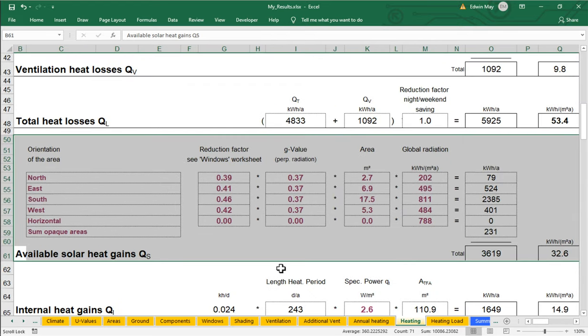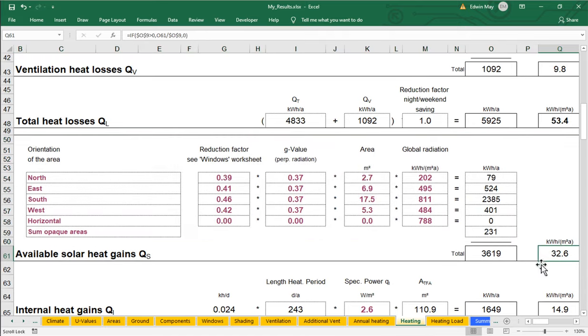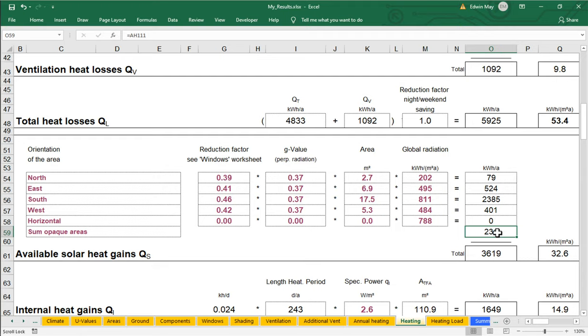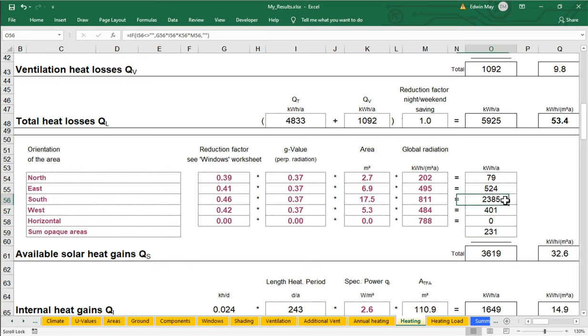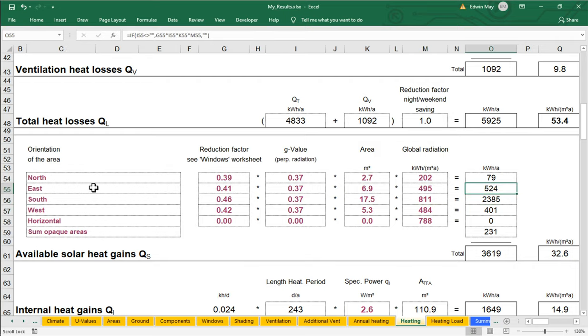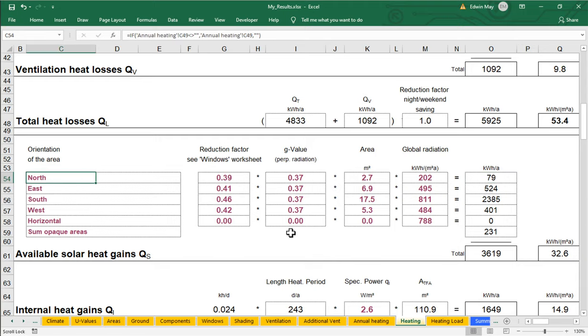So what do we see here? What is this calculation showing us? So first of all, we have a total solar gain of 3600 kilowatt hours per year. That's made up of a couple hundred kilowatt hours through the opaque assemblies, because they heat up in the sun. Zero horizontal, so zero through skylights. We don't have any skylights in the project. 400 kilowatt hours through the west-facing glazing. About 2300 kilowatt hours through the south-facing glazing. 500 kilowatt hours to the east-facing glazing. And maybe 80 kilowatt hours through the north-facing glazing.